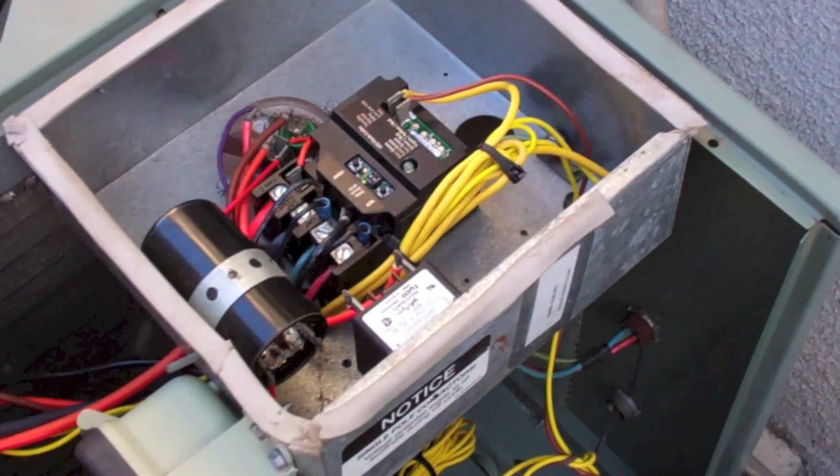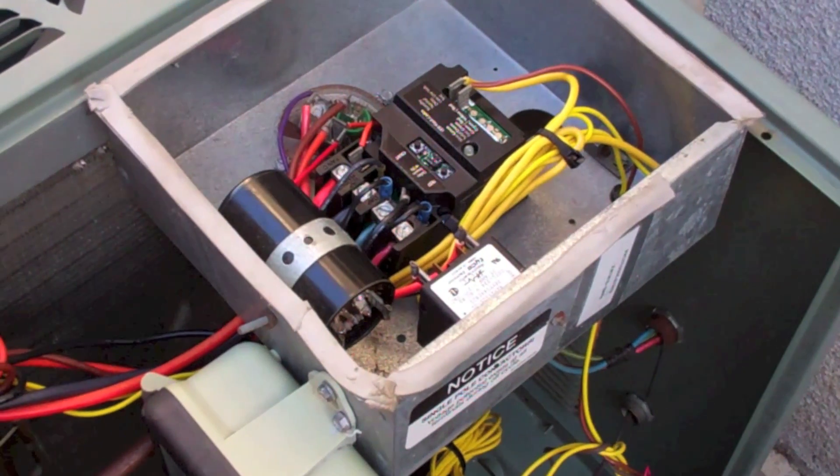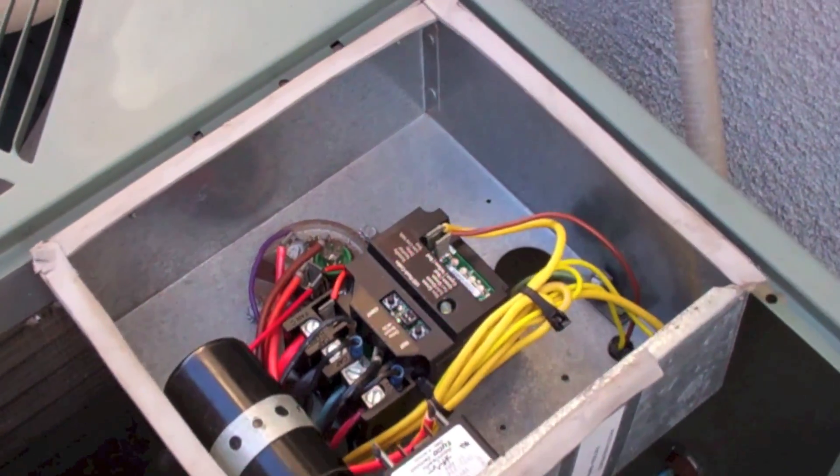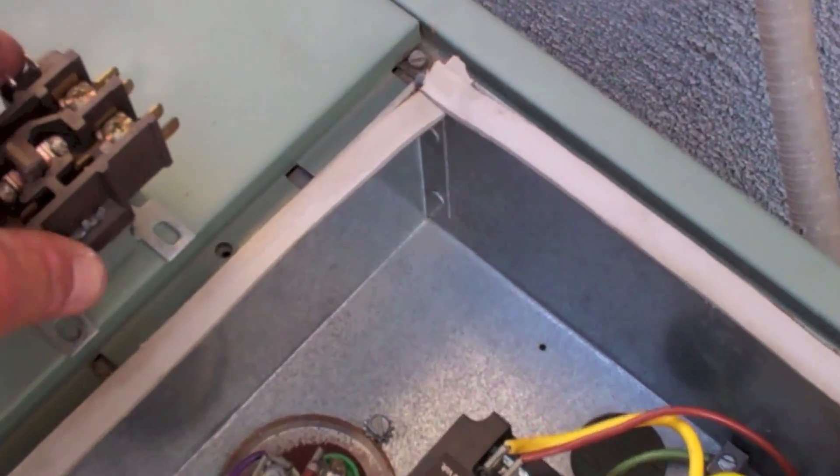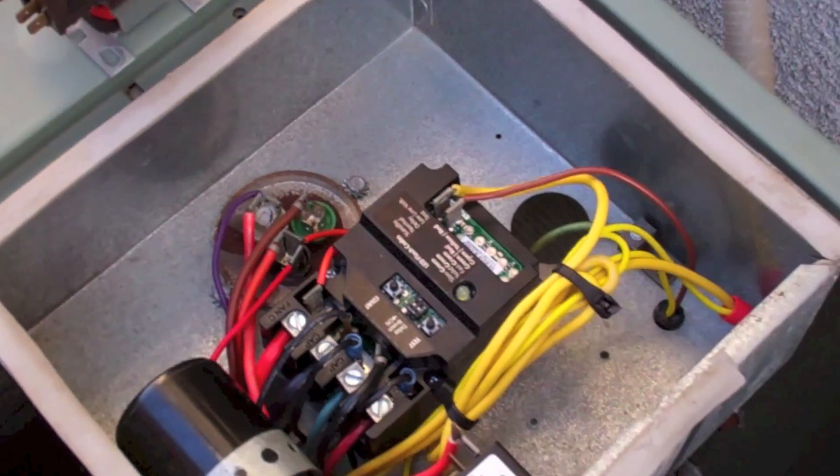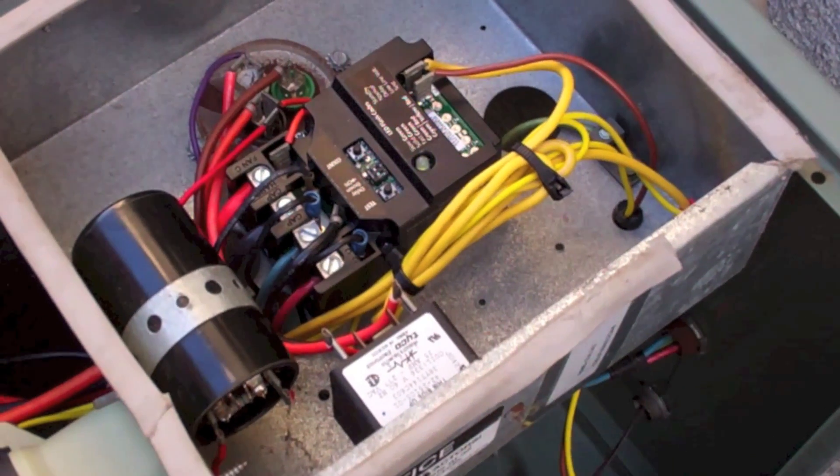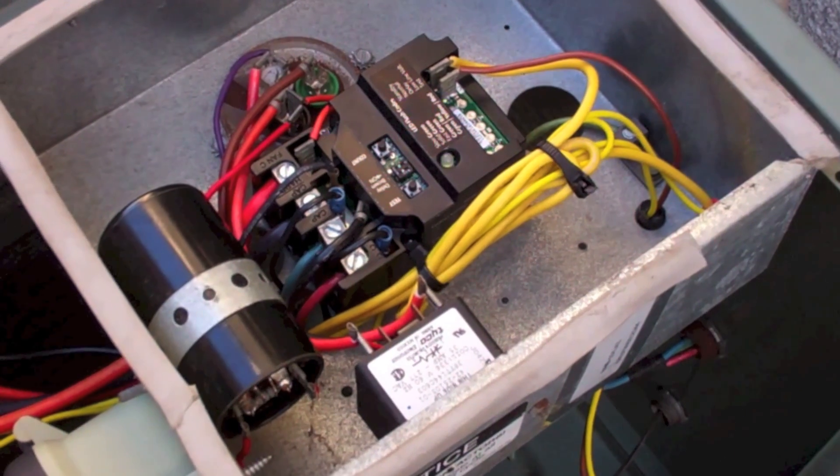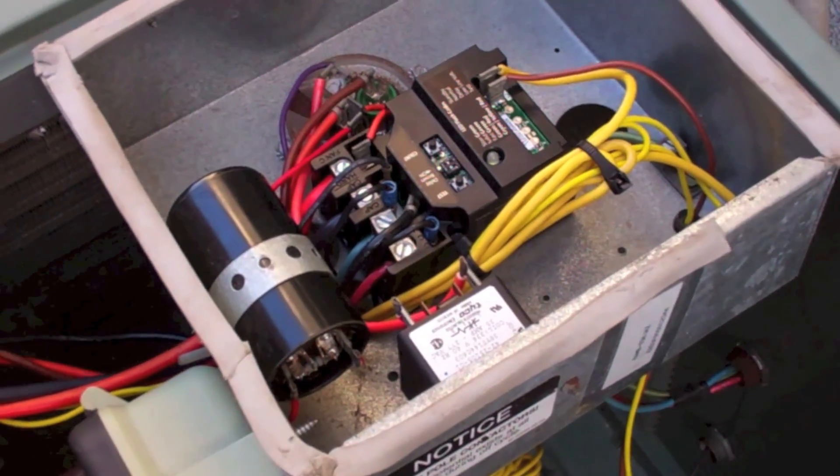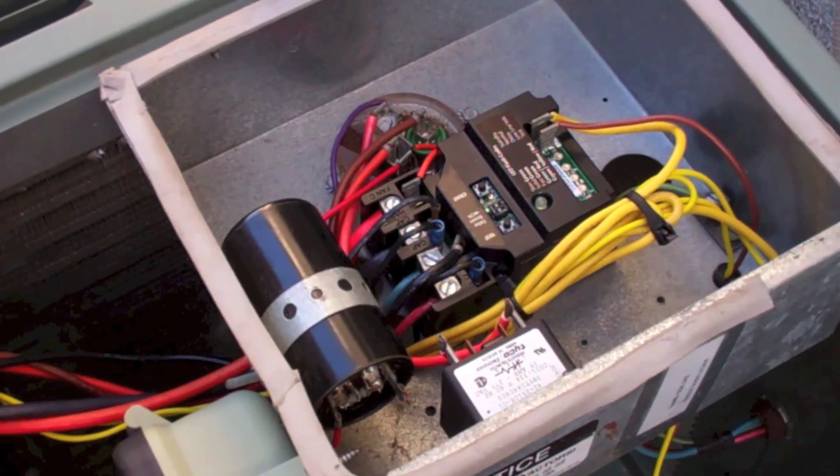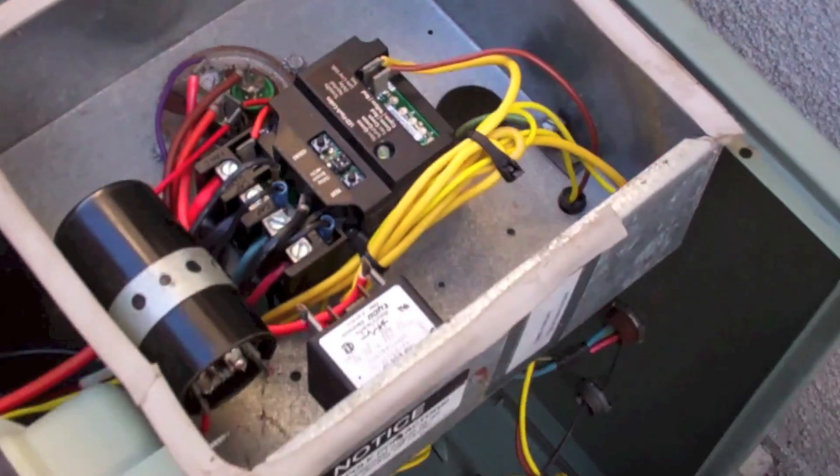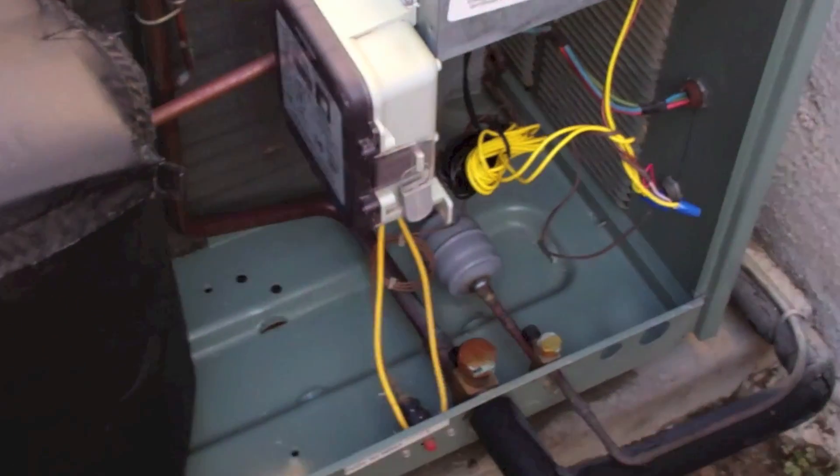I'm gonna wait for this thing to fire here, but the old contactor was always lazy pulling in on this unit. This thing just fires like brand new - put life back into the condenser. But I'll show you that 230-volt delay. It's really cool. Three minutes isn't that bad either.